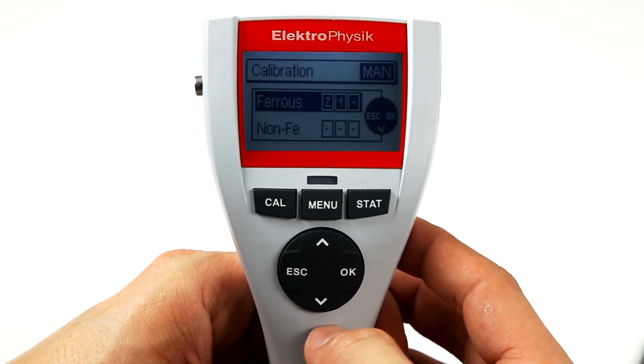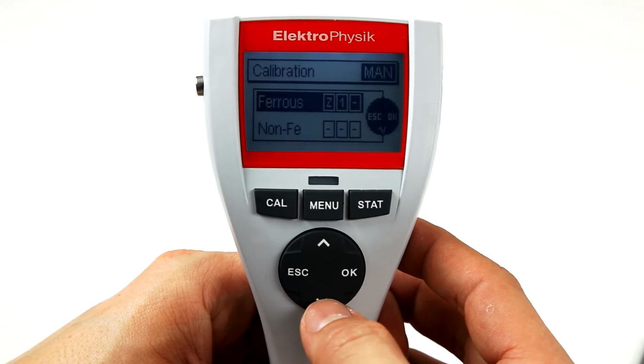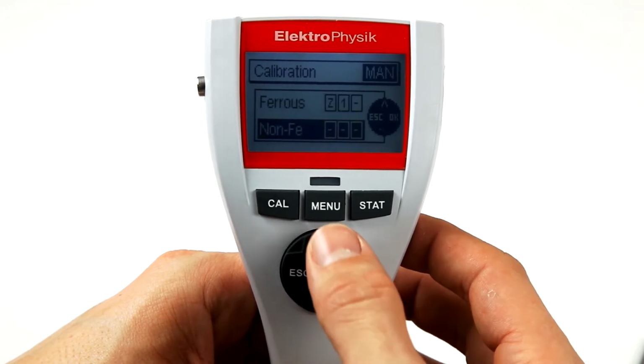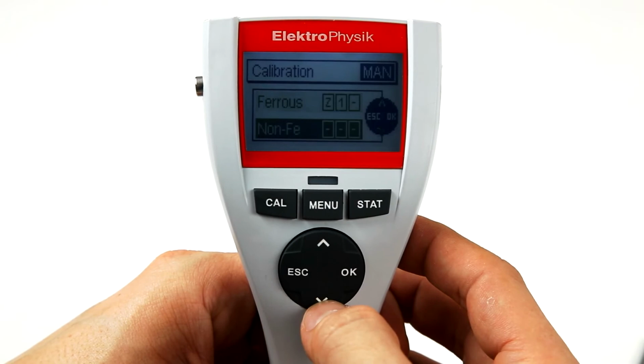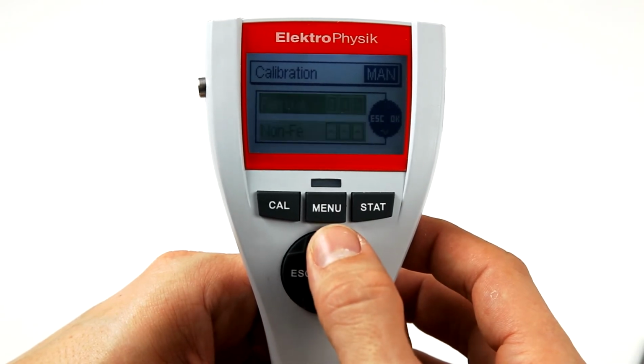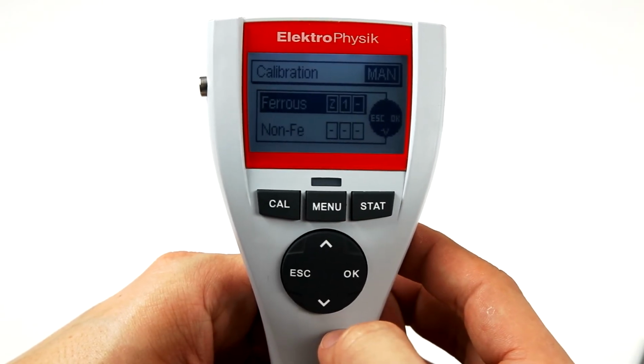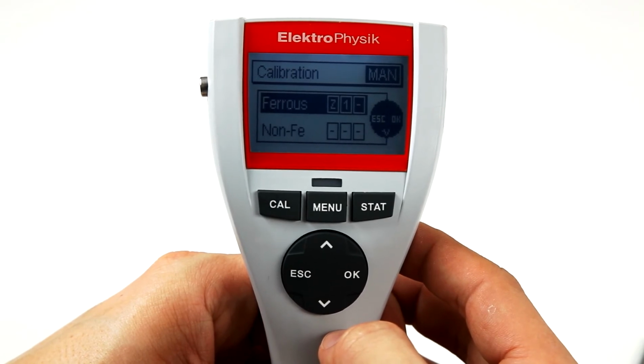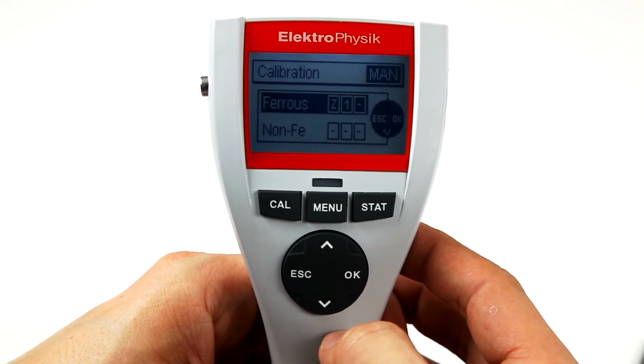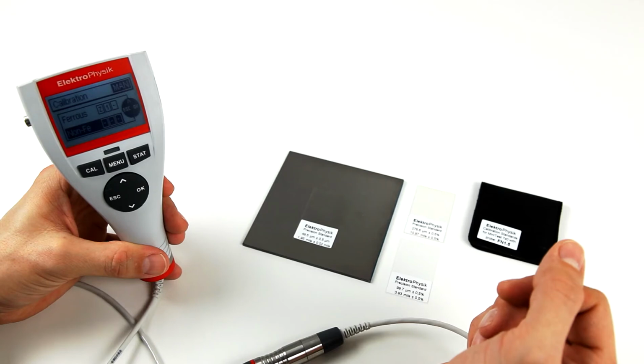The gauge will now give you the option to select between a calibration on magnetic substrate and on non-magnetic substrate. In order to perform a further calibration on a non-magnetic substrate, select the corresponding option, or quit the calibration process by pressing the Escape key.